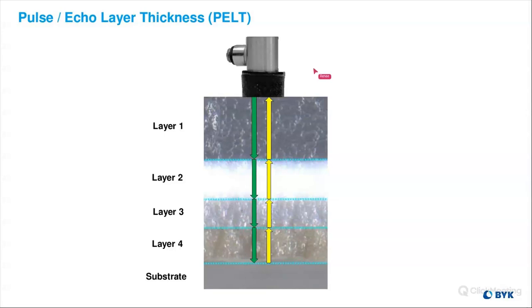It's very similar to when a pregnant woman goes to the doctor to get an ultrasound, they put the gel on her stomach before they use the probe wand. It's the same idea. We put water on the top of your finished product, and the sound will then go down through each coating. And when it hits a layer boundary, the sound will reflect back up into our transducer. So the gauge is sending out pulses of sound, and it goes down, hits a boundary, and comes back. So it does that all the way down through every coating layer until it hits the substrate.